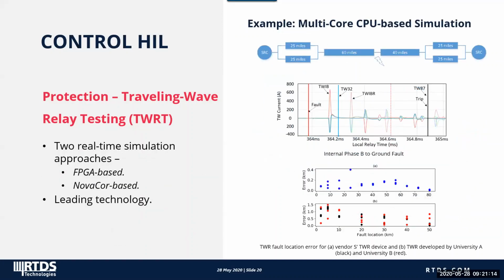RTDS provides 2 real-time simulation solutions for traveling wave relay testing. One is based on the FPGA unit, which is referred to as FPGA-based TWRT. The other is based on the NovaCor, which is referred to as NovaCor-based TWRT. The FPGA TWRT solution is for small-size systems that may have up to 4 line segments. The whole power system is simulated on the FPGA hardware with a fixed time step of 1.54 microseconds.